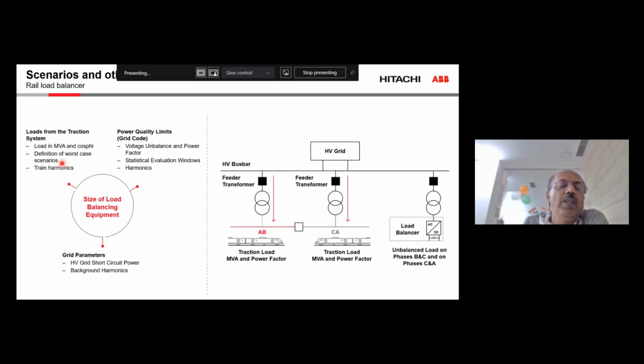For example, at 220 kV it can be 1%, and less than that can be even 2%. And then what are the power quality requirements, for example voltage unbalance and power factor requirements, and what is the evaluation window as per IEC.